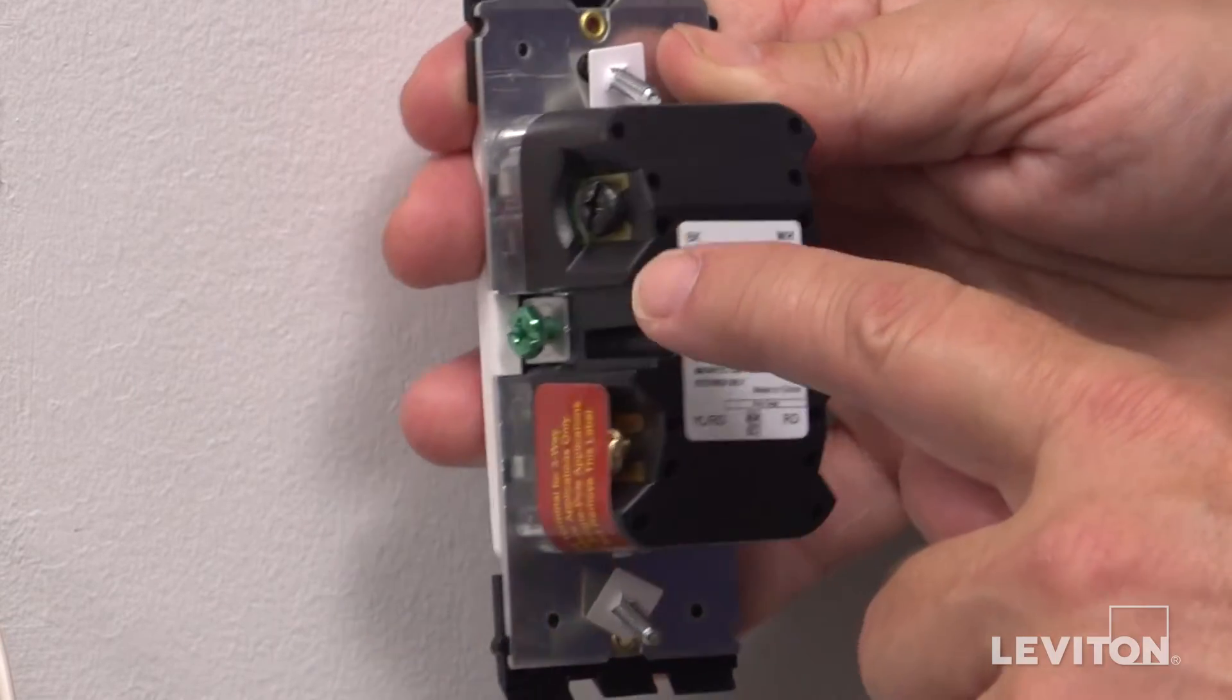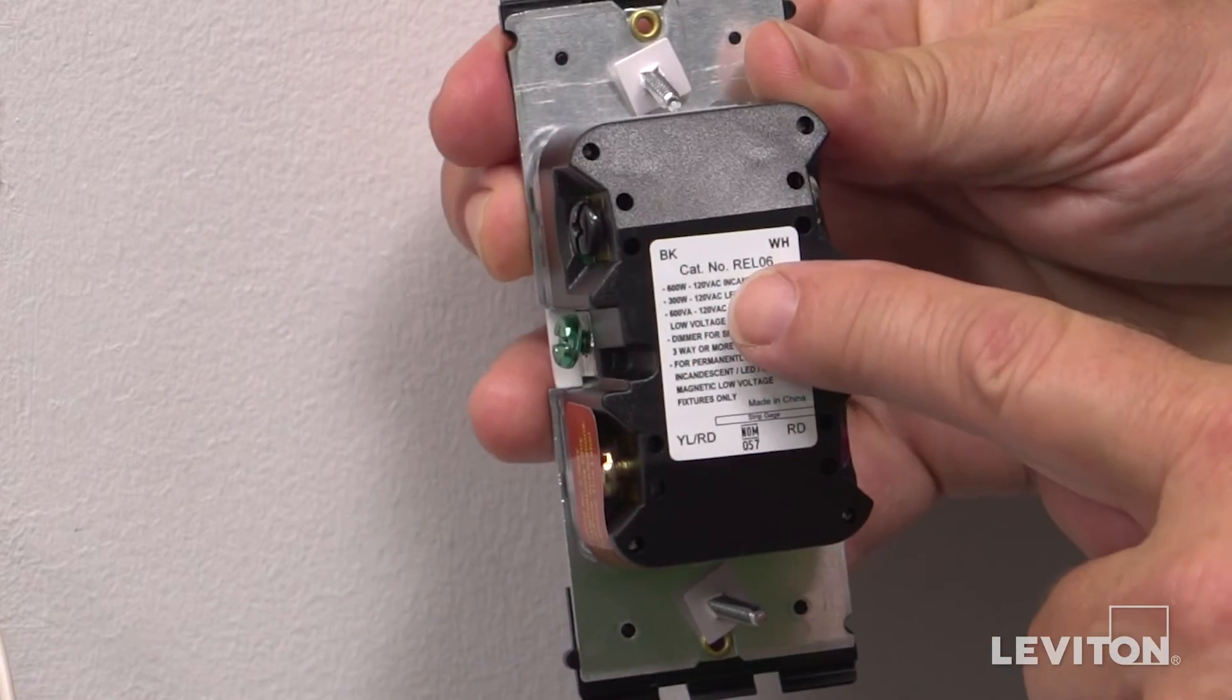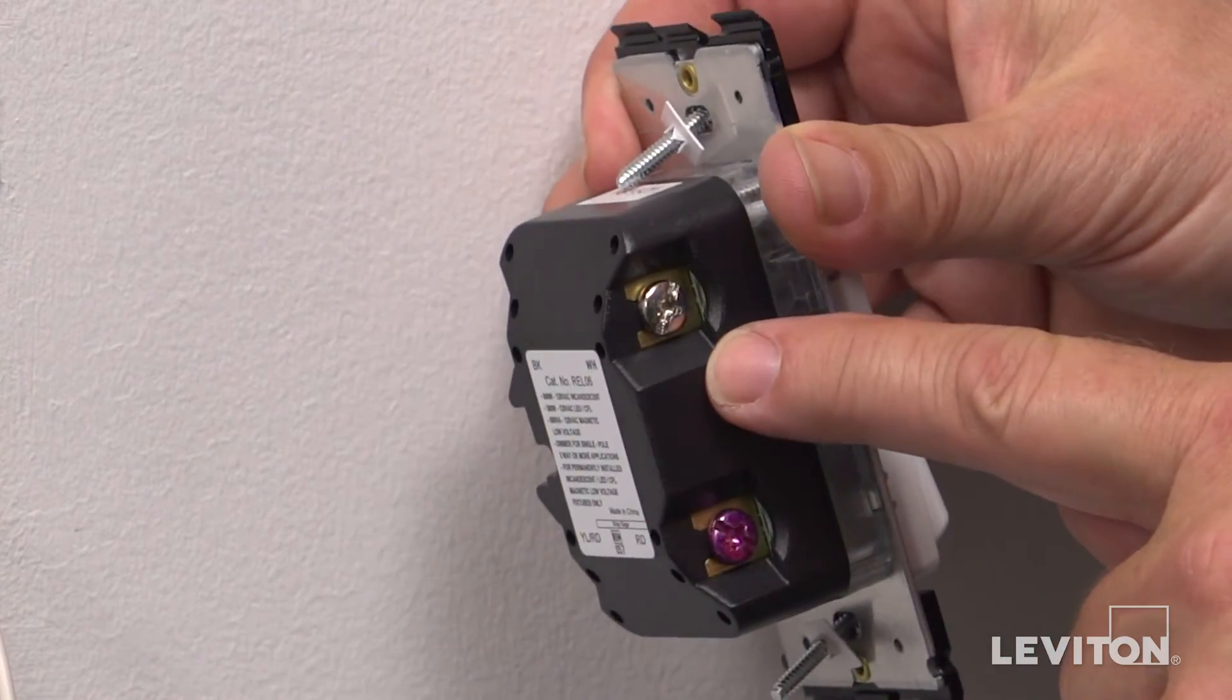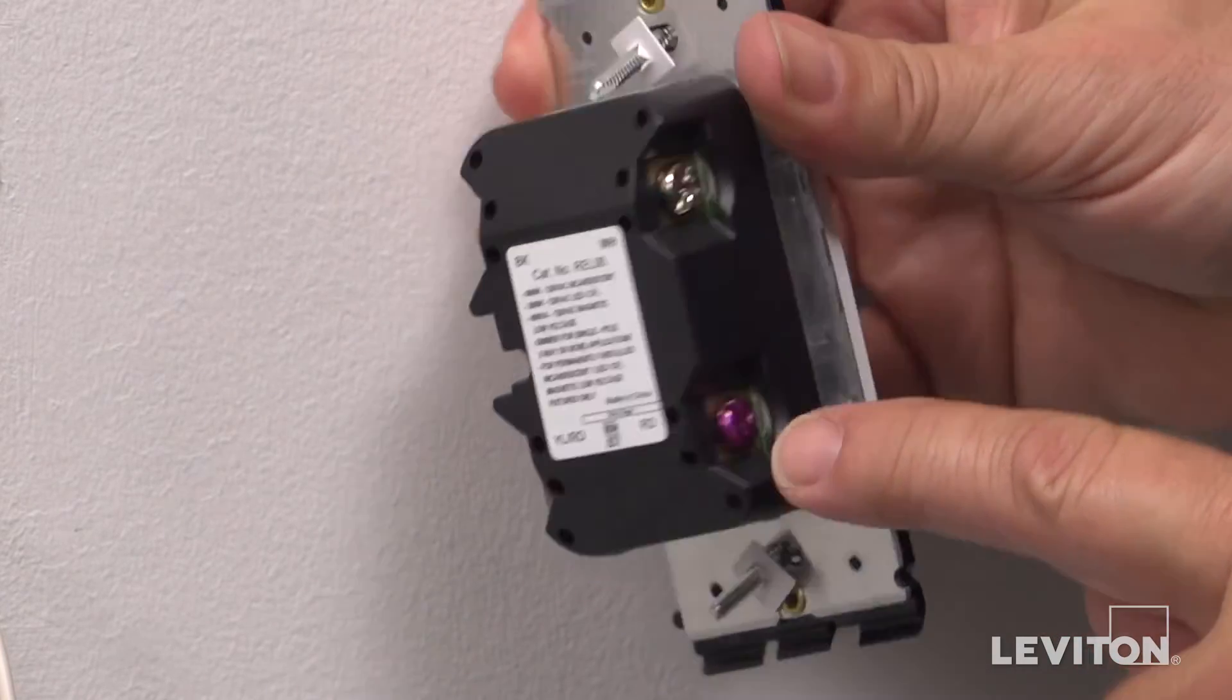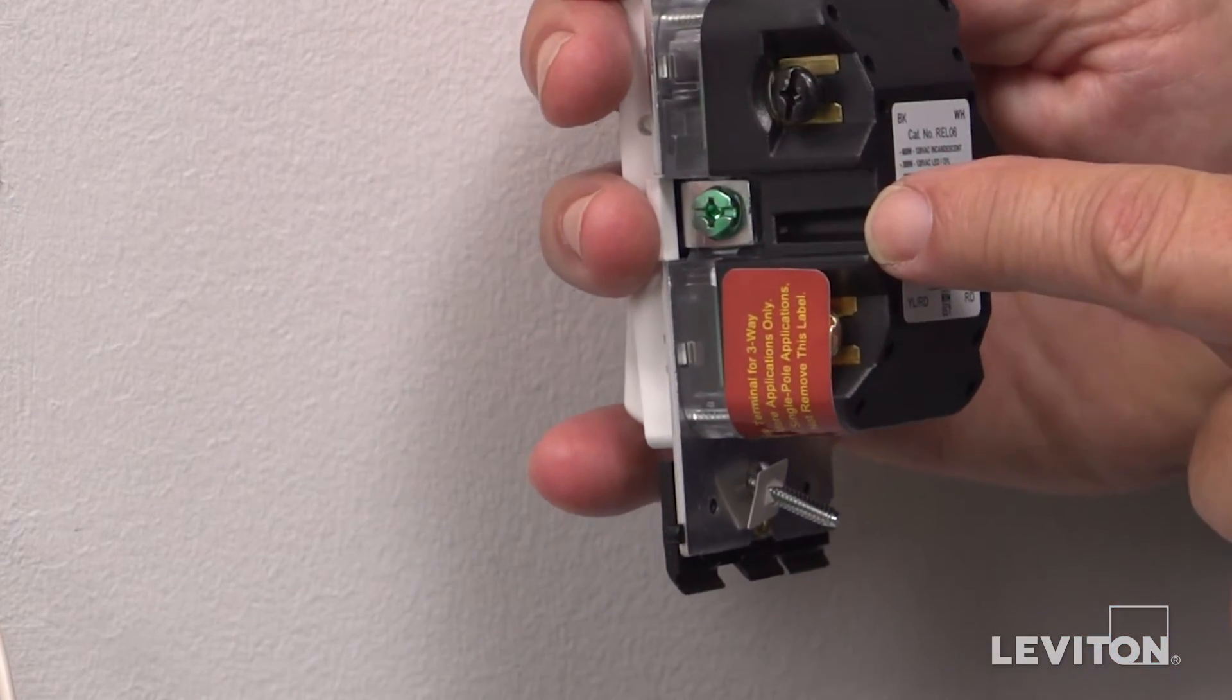The black or BK is for the line or hot wire. The white or WH terminal is for the neutral wire. The red or RD terminal is for the load and the green terminal is for the ground wire.